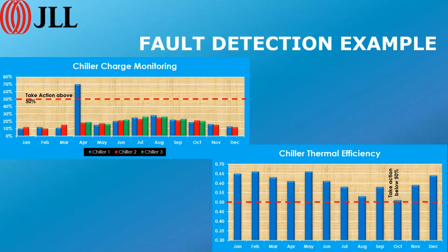Now the last one we want to look at here is fault detection, and this is a pretty good example of how fault detection works. This is off of an air-cooled chiller. It's got 3 compressors in it, and in this case we're monitoring something called delta P over P. So we're looking at the condenser pressure and the evaporator pressure. We're looking at the difference between those two, and we divide that number by the evaporator pressure.